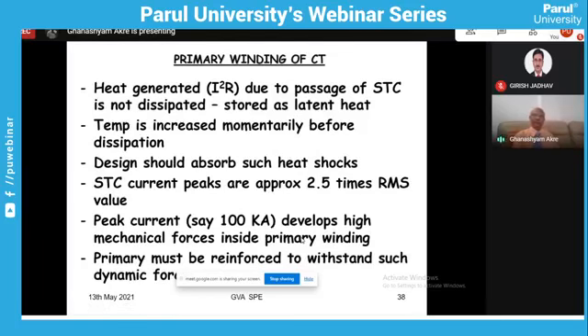Also, the heat which is generated during the STC, that short circuit heat, is generally not dissipated, whether it is a 1-second or 3-second rating. The full primary is insulated by paper insulation, so in that case there is no possibility of any dissipation. Hence, the total primary takes that heat as latent heat, and the temperature of this winding can instantaneously rise very high, causing burning of the insulation surface. And that is why the formula which I have shown you is very important.